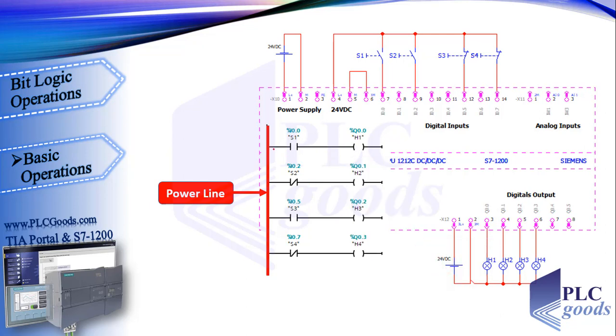Now see the first line. The power can reach to here. The question is: how can we change the state of this contact in a PLC program? In real, we press push buttons or switches. In PLC programs, each contact has an address which has two states — 0 and 1, or true and false. This binary address is I0.0, which refers to this PLC input. In this wiring, the 24V DC cannot reach to this address, so the state of I0.0 is false or 0, and this contact will be in its normally open state.